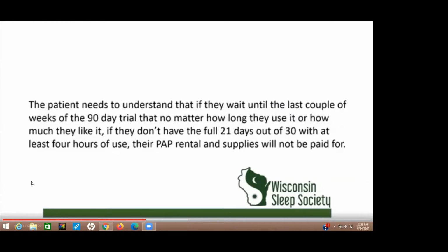As I said before, compliance is defined as wearing it 70% of the time in a 30-day period of the first 90 days after setup. So the patient needs to understand that if they put it off and don't make a successful attempt to use the device until the last couple weeks of the 90-day trial, no matter how much they wear it or how much they like it or how well it works, they are not going to achieve the full 21 out of the 30 days with at least 4 hours of use, and their PAP rental and supplies will not be paid for.